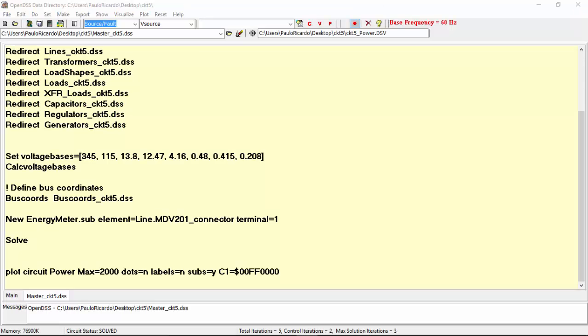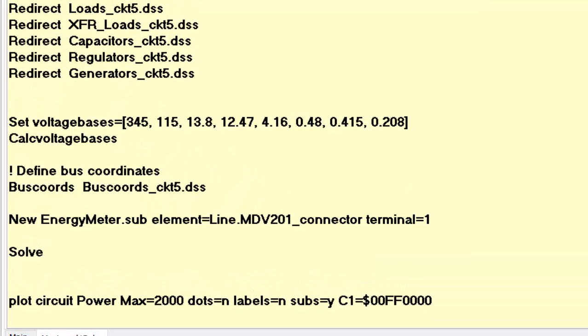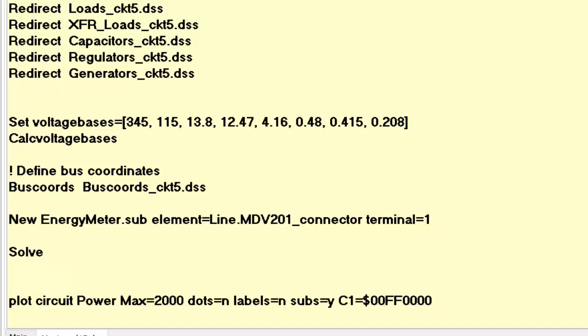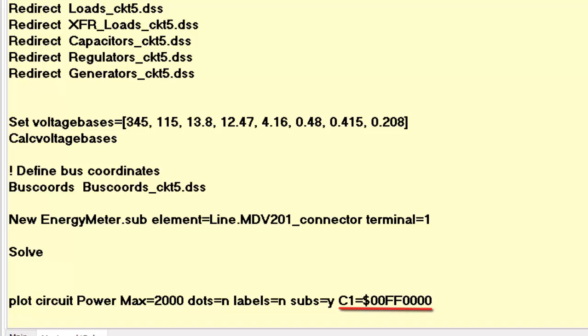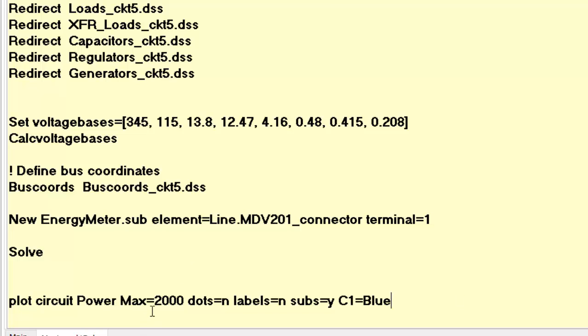As we left the record command activated, the plot command that corresponds to the options we have selected has automatically been recorded at the bottom of our script. As you can see, we have performed a plot command in which the line thickness represents power with a maximum scale of 2000 kW. The options dots and labels have been set to no and the subs option has been set to yes. C1 is the color used for the lines. The default color is blue. The color may also be specified either by its RGB color number, as this case, or standard color names, for example, blue. In the OpenDSS manual, there is a list with all standard color names.